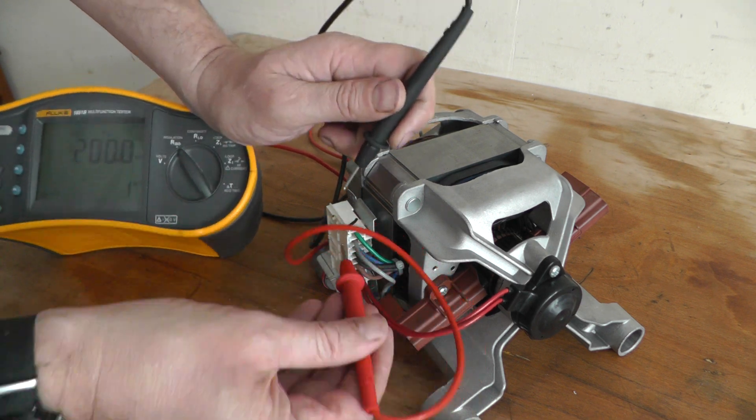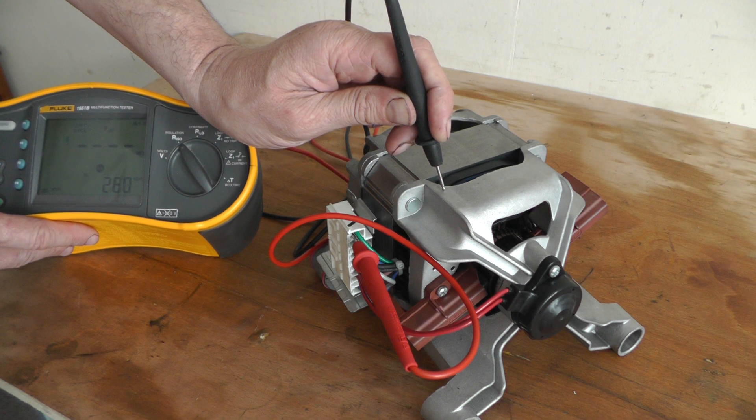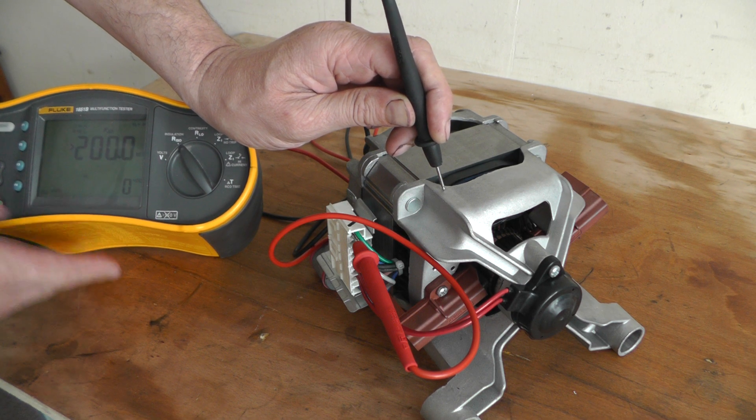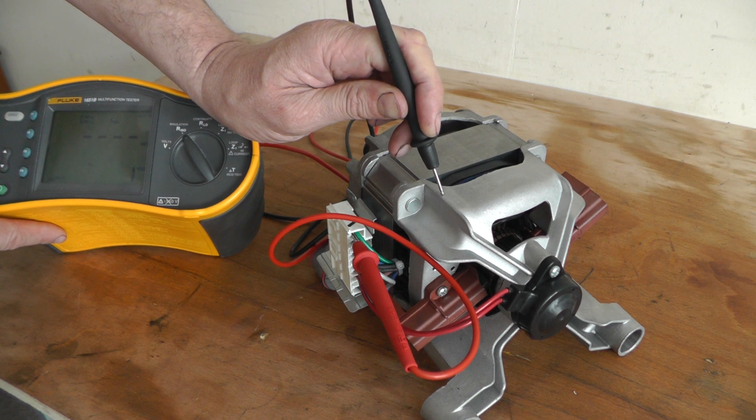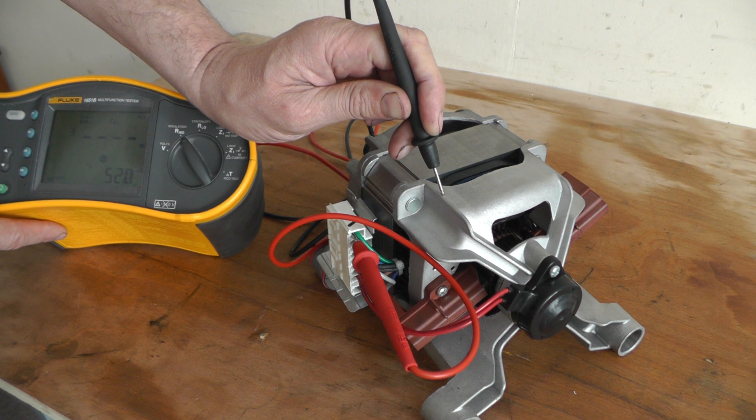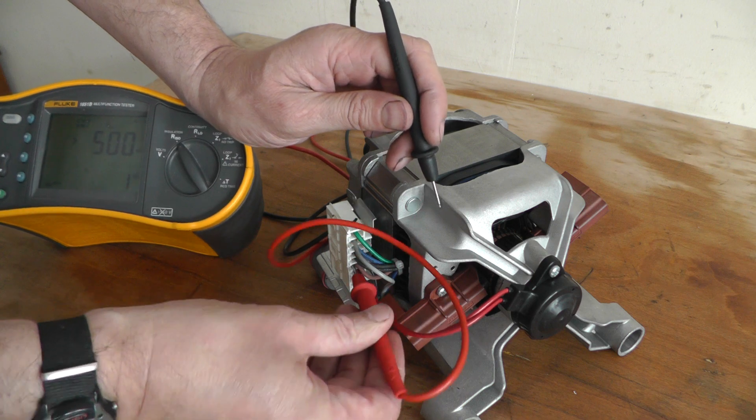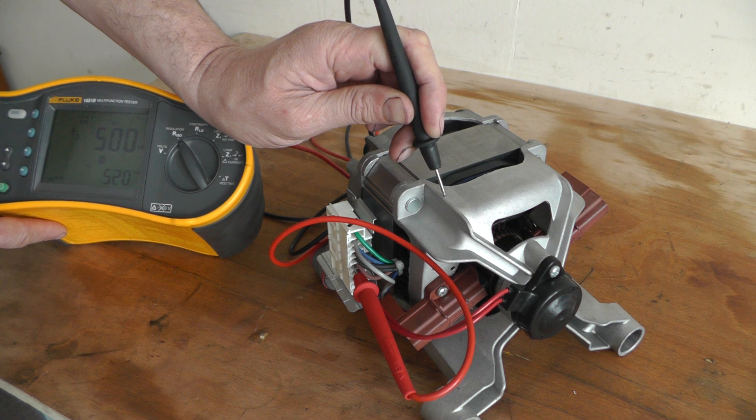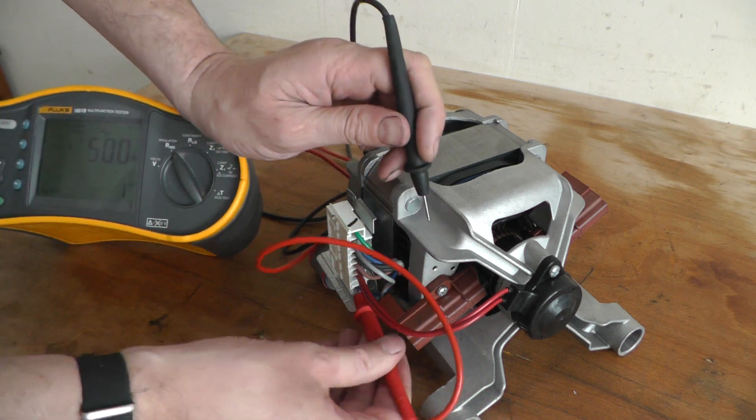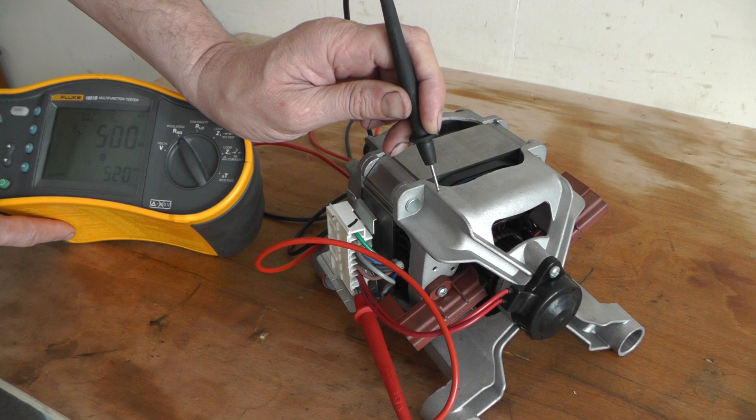Greater than 200 volts, so I'll do them all again but this time at 500 volts just to make sure. It should be greater than 500 now. Yep, greater than 500 mega ohms. And again on the second winding, and again on the third winding.